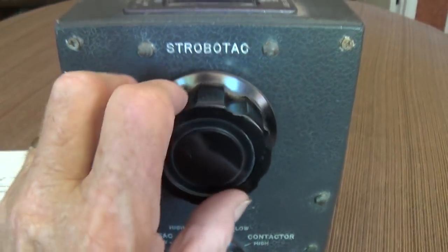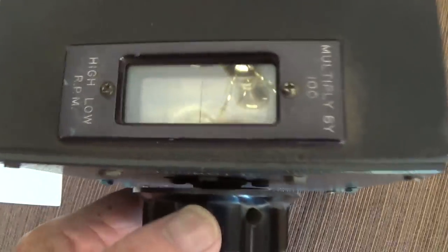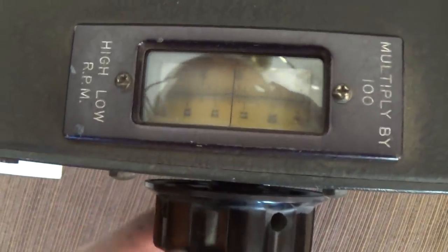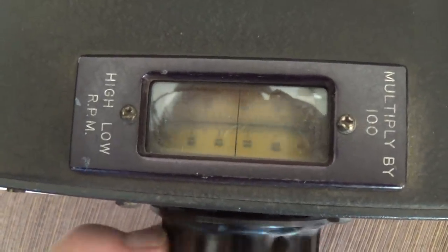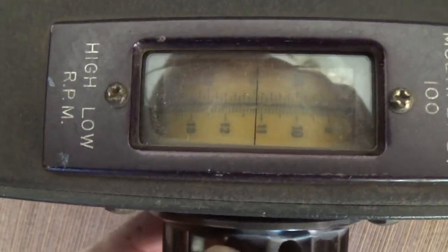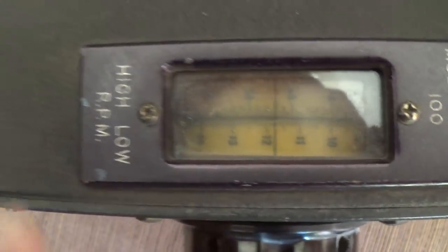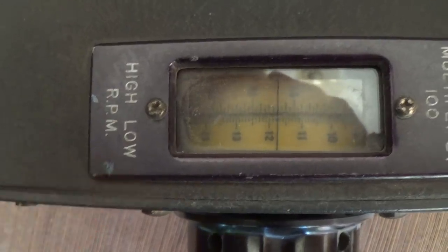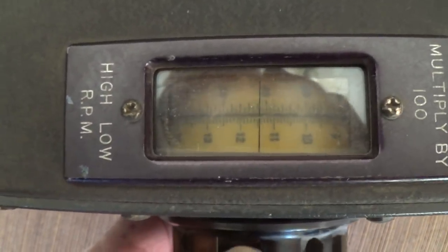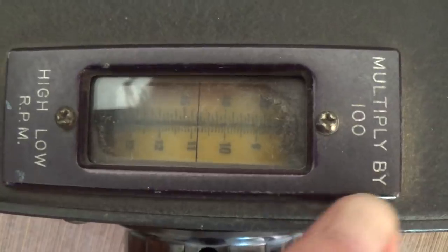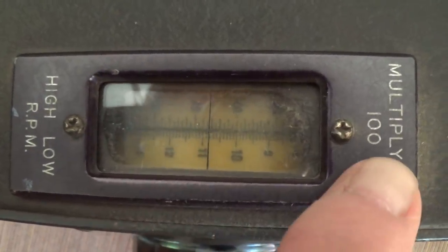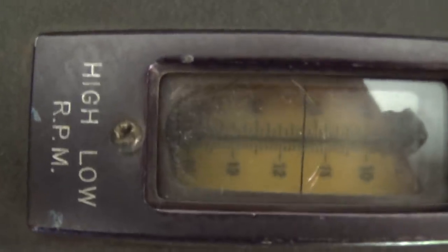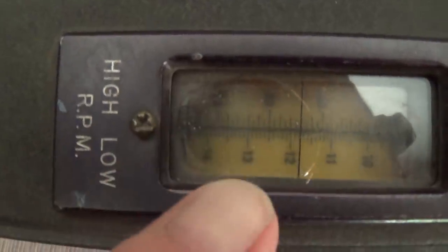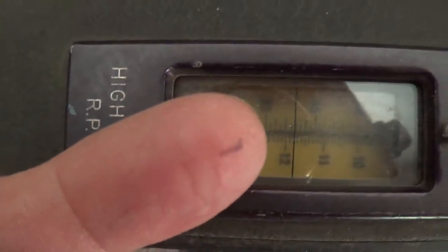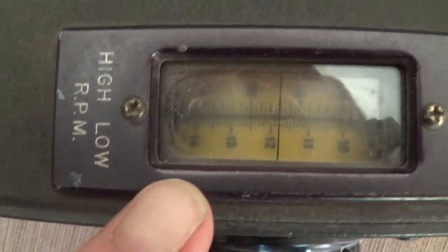This big knob is the way that we will change the speed of the strobe to match the rotational velocity of whatever it is that we're studying. And you'll see that up here we have a high and low range for RPMs. And also these are just 2-digit numbers. We have to multiply by 100. Now there's the high scales over here, low scales here, and it's backlit because it's best to use this device in the dark, so you have to be able to take your readings.